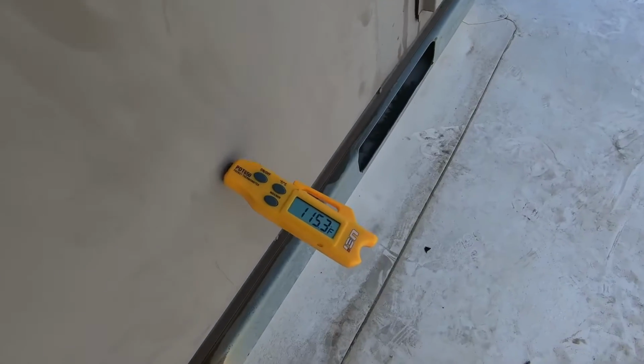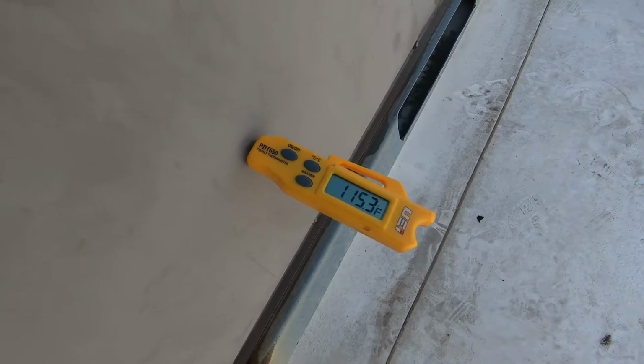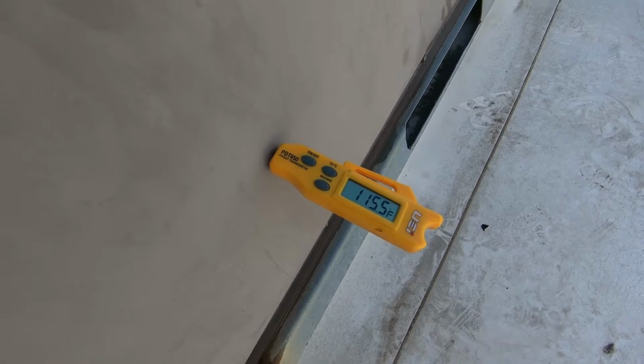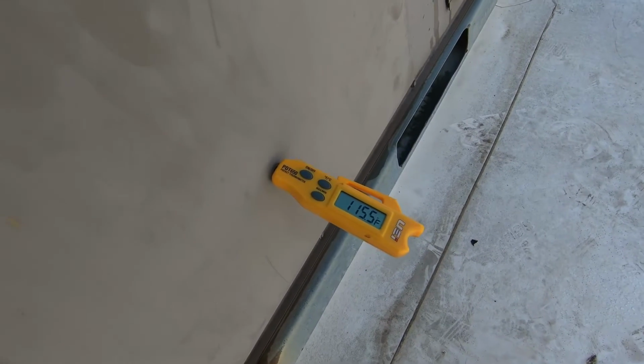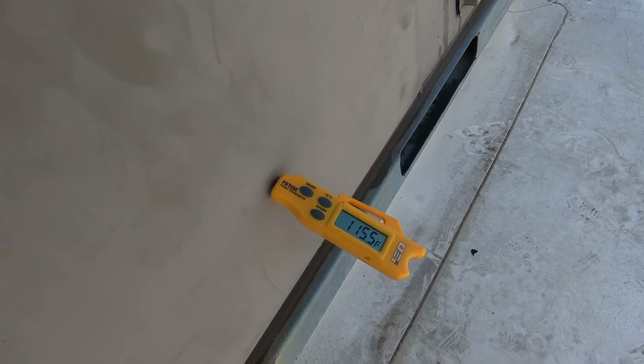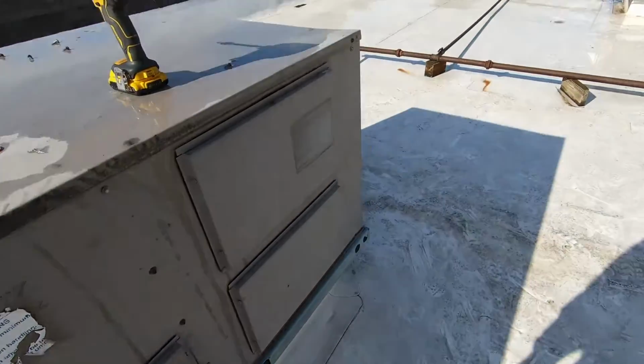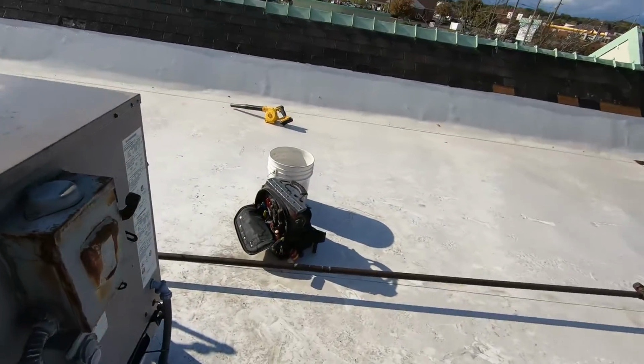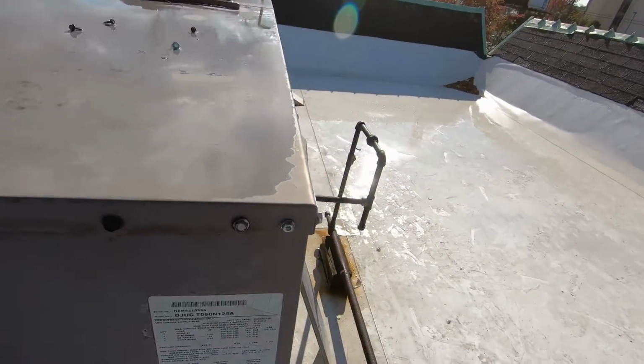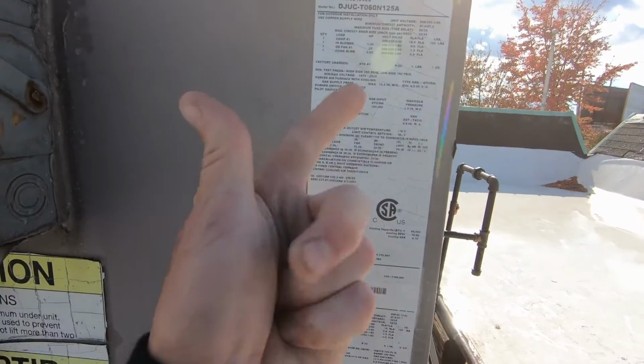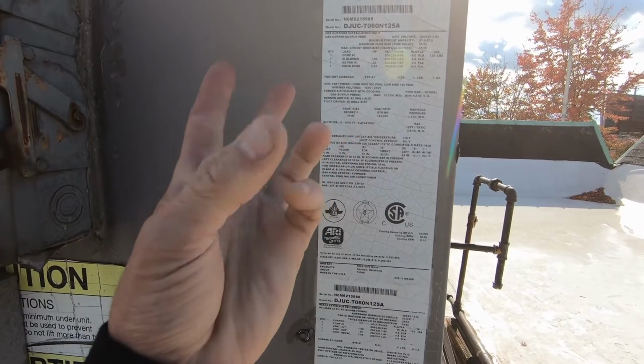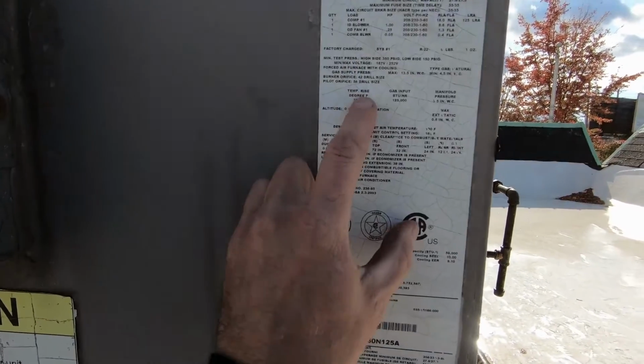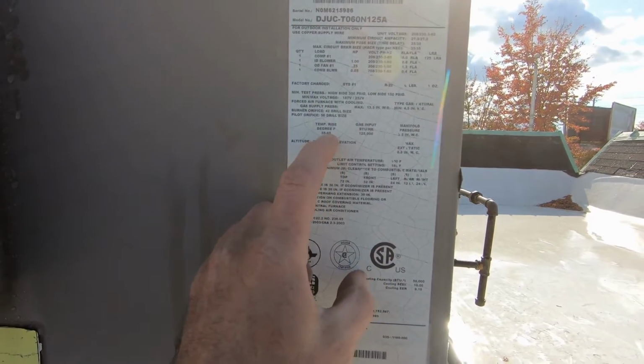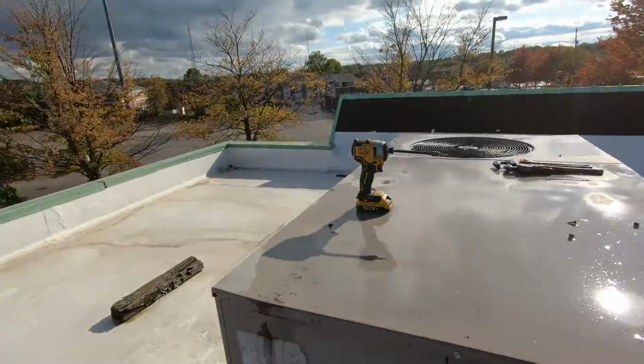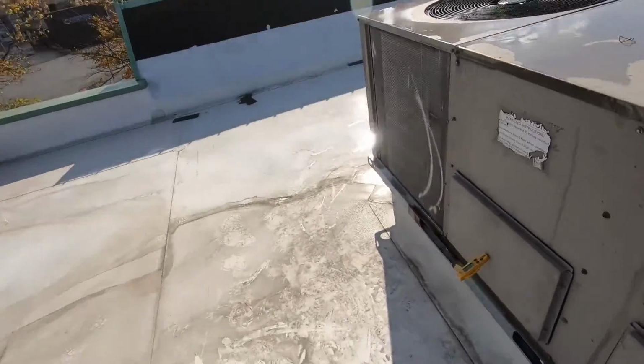And it looks like we're slowing down around 115. So that's gonna be about a 45 degree temp rise. 115, I like it. 70 degrees, I'm calling it 70, it was 69. So 70, 80, 90, 100, 110, 115, that is 45 degree temp rise, and we're good for 35 to 65. I think we're in good shape. We've not had many issues with this unit before.